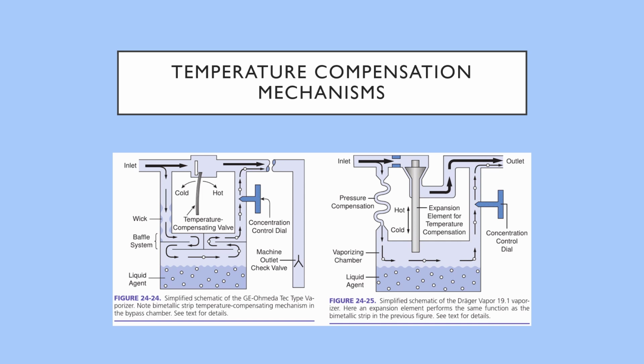Mechanisms can be either a bimetallic strip, which is seen on the left here, that basically adjusts its position in relation to the temperature, or an expansion-contraction element, which is this cone-type design on the right.